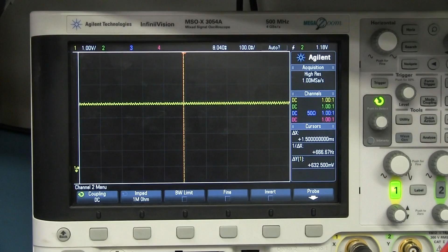And if you're curious to see how quickly this discharges, well, let me unplug it. And it's still holding a decent charge - look at that. This is why you don't want to touch these things unless you've left them off for quite some time. It's also recommended you put a dummy load across them, a big resistor calculated so you can put it across there and drain that main filter cap. But look at that, that main filter cap has still got 260, 270 volts DC on there. That'll give you a hell of a belt.